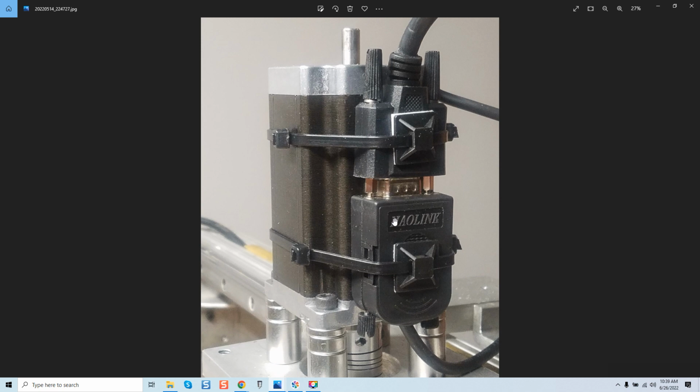What this is essentially doing is, once again, you're not only taking the actual cables and resting them against the motor, where we're really just mitigating any type of cooling for the motor, and you're excessively applying massive amounts of heat to the cable, but we're also employing a lot of stress with the zip ties, and we're putting excess stress on these jack screws and jack nuts. So again, this is not best practice, guys. Organize your system and really think about your cable placement.